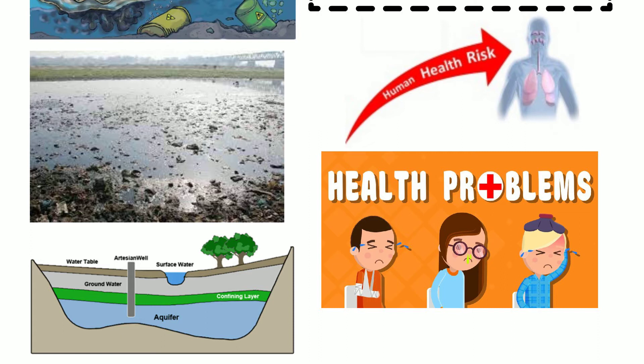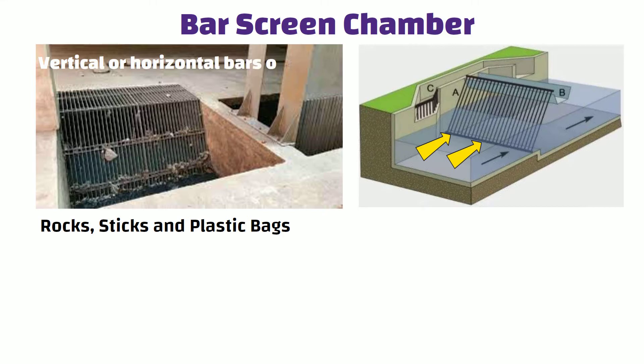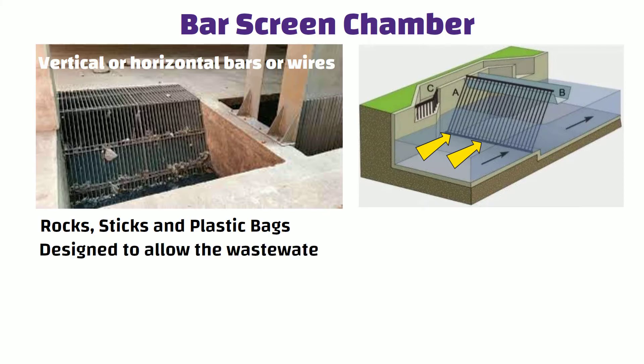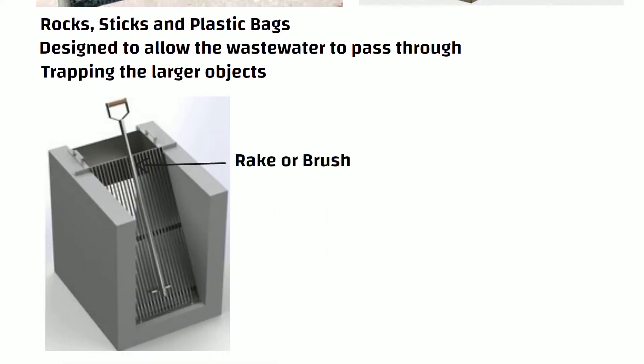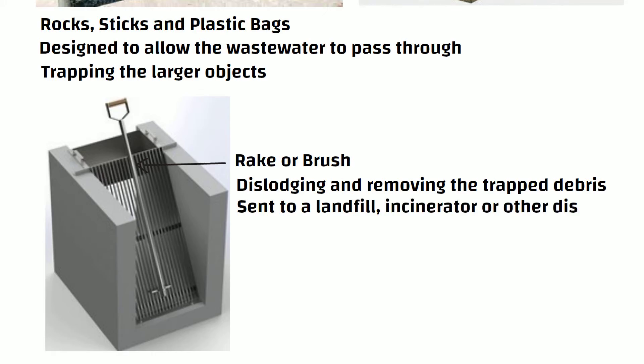Now let us discuss each component of STP in detail. Bar Screen Chamber: as the waste water flows through the bar screen chamber, any large objects such as rocks, sticks and plastic bags are trapped by the bar screen. The bar screen consists of a series of vertical or horizontal bars or wires spaced close together, designed to allow waste water to pass through while trapping larger objects. A rake or brush moves along the surface of the bar screen, dislodging and removing the trapped debris, which may then be sent to a landfill, incinerator or other disposal facility.